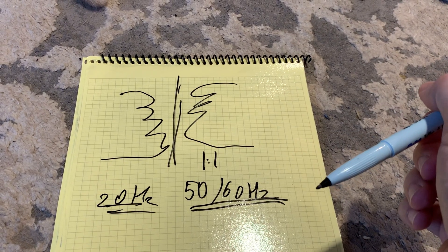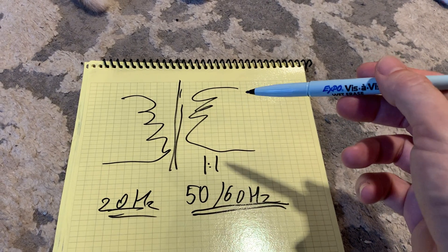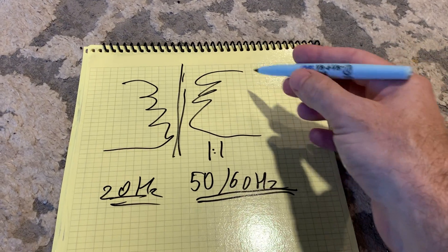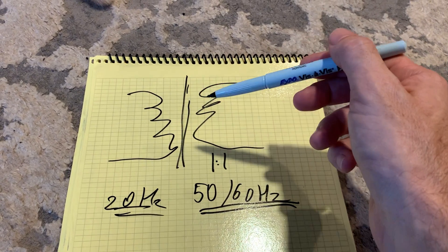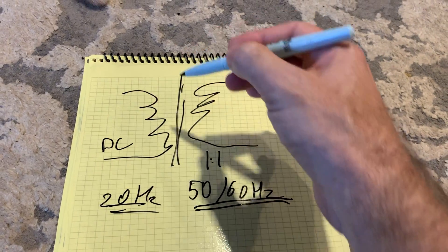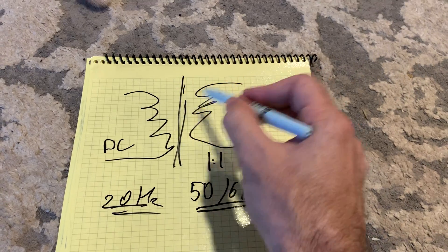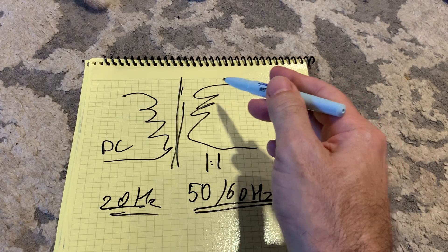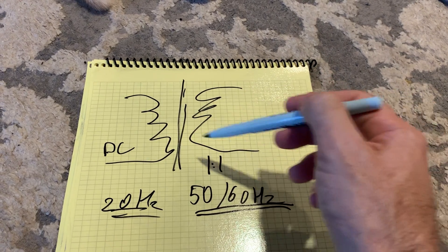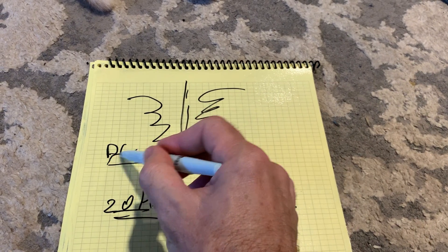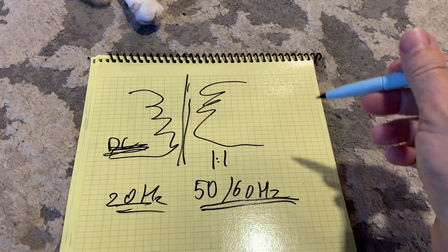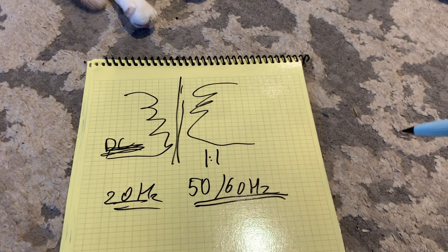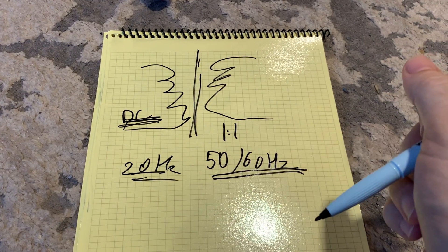Does that solve the problem of DC being present on your line? To a certain degree, yes, because the equipment is going to get pure AC - it's not going to get the DC component. Yet the problem is that when there's DC present on the mains line, the DC component will magnetize the iron core of the transformer, and it will not be able anymore to pass on high current for the secondary. Basically, the DC present will overload your transformer and lower the efficiency. That's one issue why an isolation transformer is not a fix-it solution for DC present on the line.